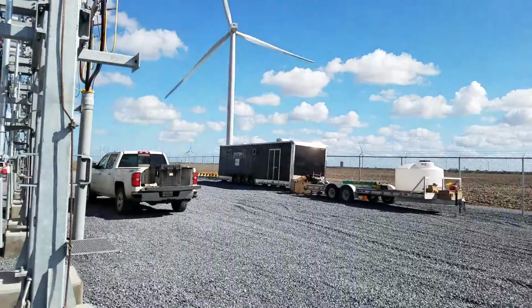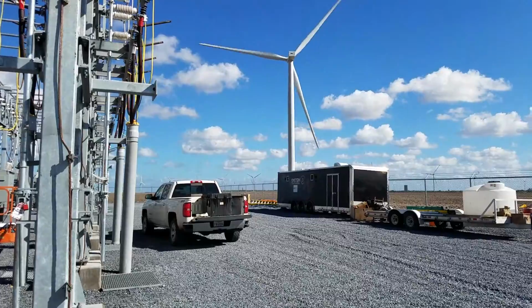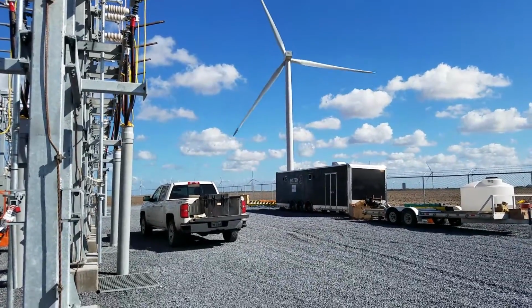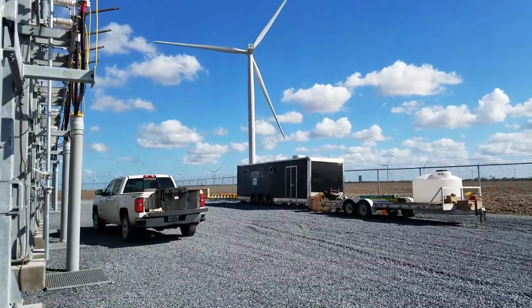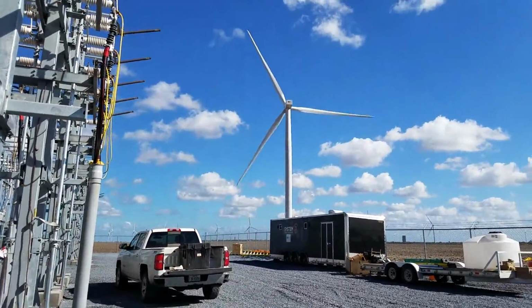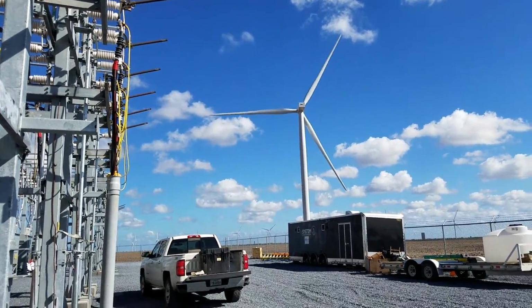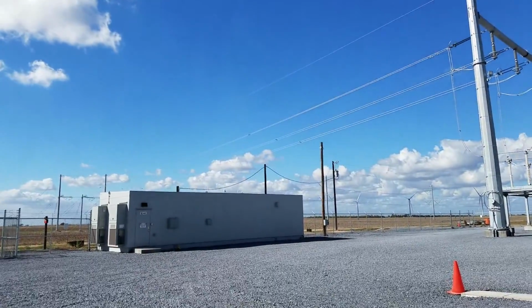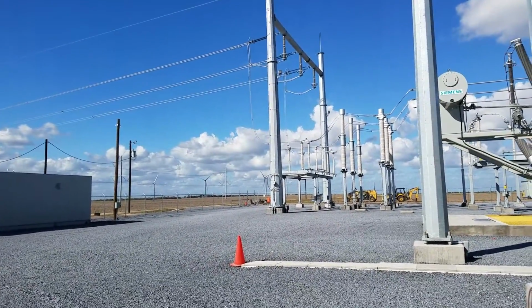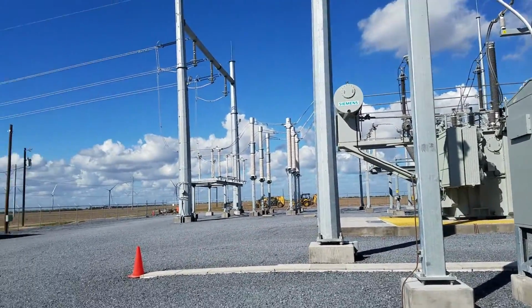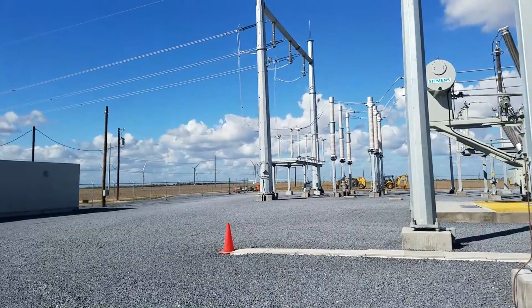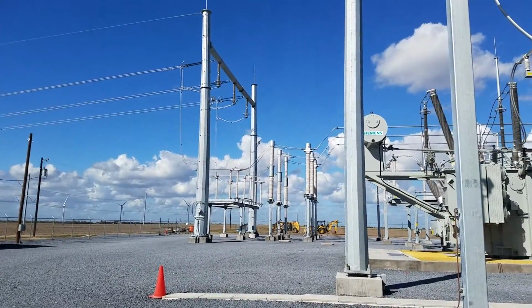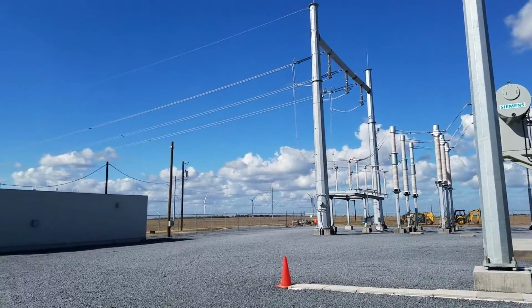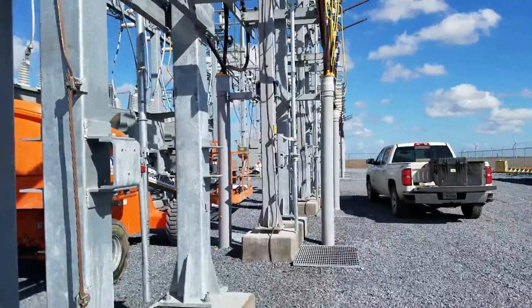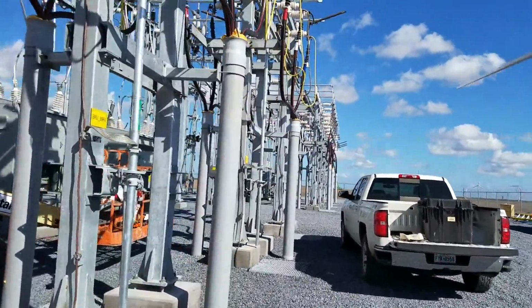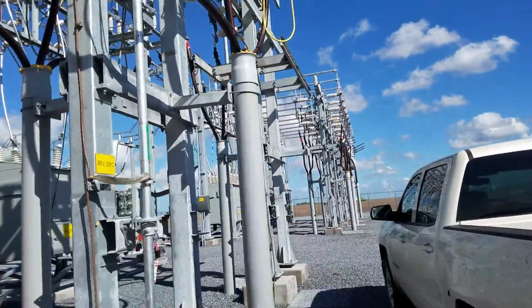And you need those to keep the correct power factor that the utility wants, because when these turbines speed up and slow down, you need that capacitance to regulate the voltage. You don't want it to drag anything down. I think that this particular utility wants a lead and lag no greater than 0.95. 1 is unity power factor, or 100, and they don't want you to go 5% more either way, which would be the 0.95 lead and lag. But you can save that for another video. So let's walk over here to the other bay that's energized. I'll show you what that looks like.